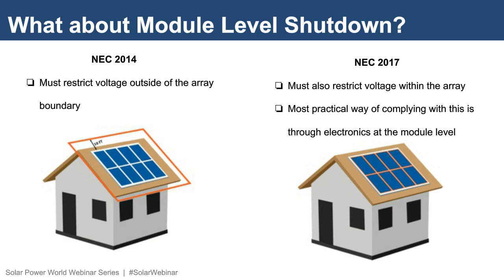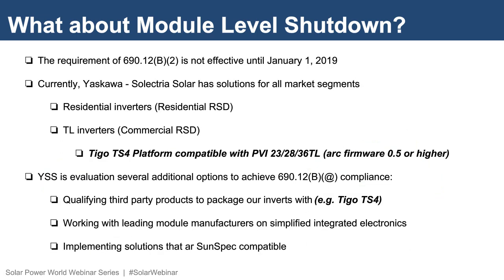Currently, Yaskawa-Solectria Solar has solutions for code compliance for all market segments. Array-level rapid shutdown for our residential single-phase product line. For residential products, our single-phase inverters, we have a residential rapid shutdown combiner. For our TL inverters, commercial industrial projects, the solutions I've talked about today.